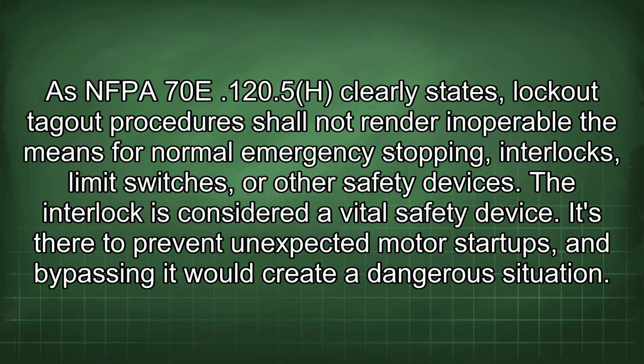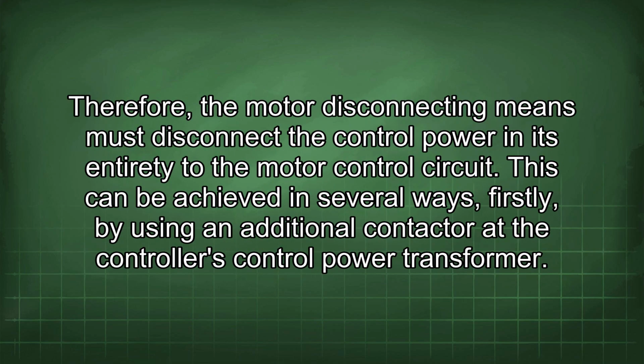As NFPA 70E .120.5(H) clearly states, lockout-tagout procedures shall not render inoperable the means for normal emergency stopping, interlocks, limit switches, or other safety devices. The interlock is considered a vital safety device. It's there to prevent unexpected motor startups, and bypassing it would create a dangerous situation. Therefore, the motor disconnecting means must disconnect the control power in its entirety to the motor control circuit.